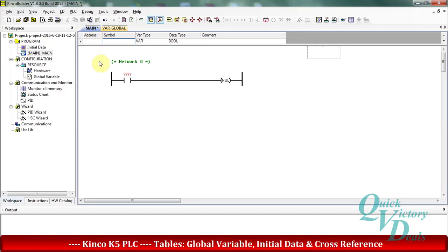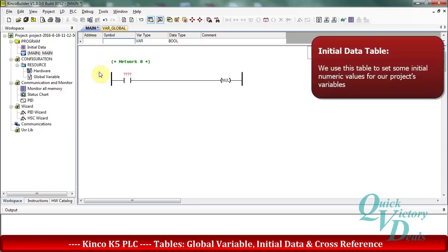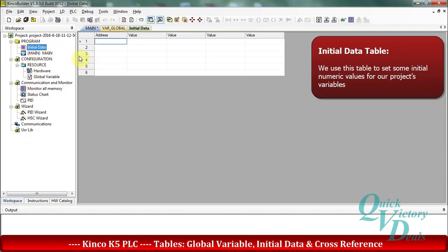In the next part we want to check the initial data table. In this table we can set some initial numeric values for our variables in different formats — for example real, double integer, integer, double word, word, and byte. Note that we can only use this table for V-memory variables.